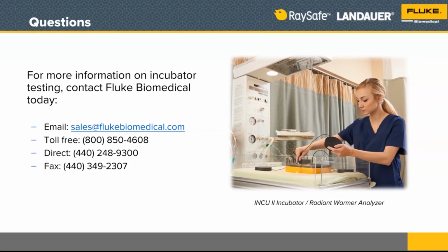Can you talk again about the placement of the temperature sensors on the mat and how to best determine where to place them? It's really this simple - you can make measurements if needed, but you can almost visualize it in your head. You want to make a temperature measurement at the center of the mattress, then imagine the mattress divided into 4 equal quadrants - even if they're rectangular rather than square, that's okay. In each quadrant, put a temperature sensor at the center. So the center of each quadrant plus the center of the mattress - that's 5 points. That matches the intent of the standards.